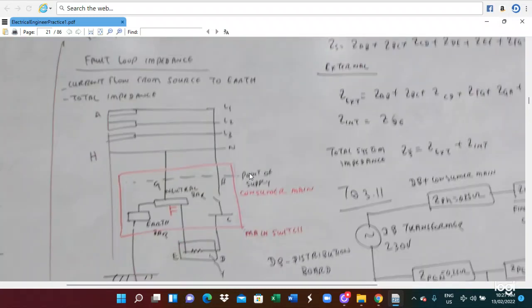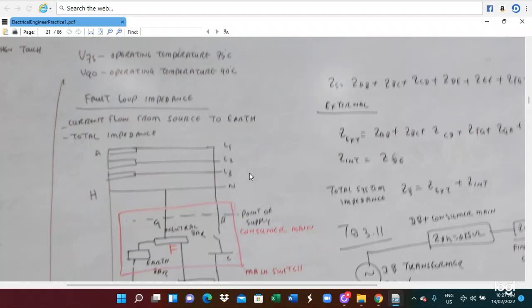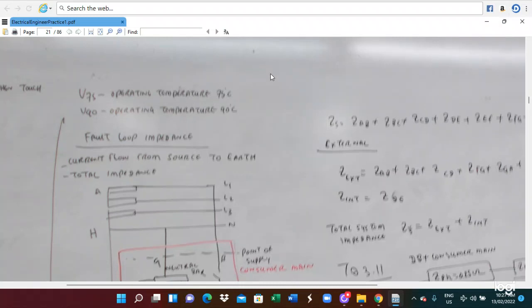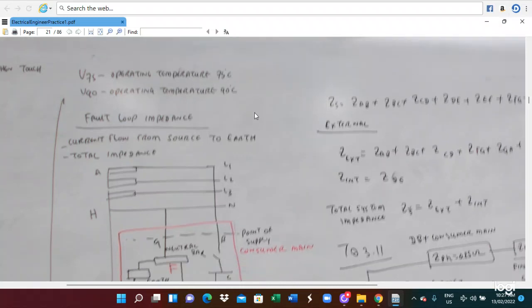Another thing is the fault loop impedance. Fault loop impedance is for the V75 operating temperature, 75 degrees centigrade. V90 is the operating temperature of 90 degrees centigrade. When we are looking at electrical cable, some cable you can see is V75, some is V90. V75's operating temperature is 75 degrees centigrade. V90's operating temperature is 90 degrees centigrade.